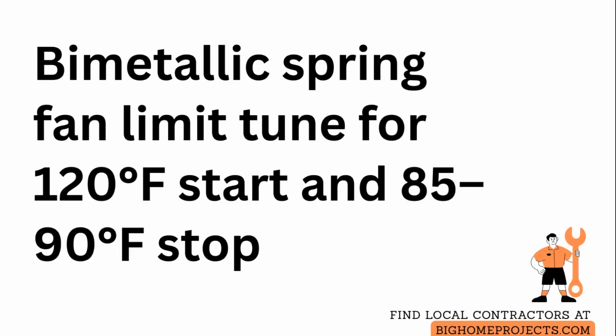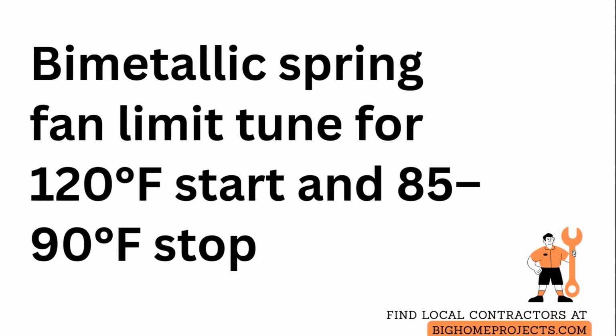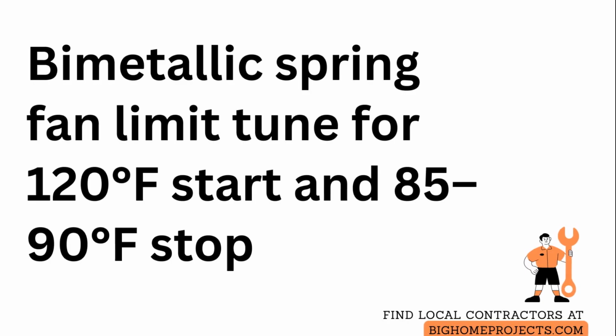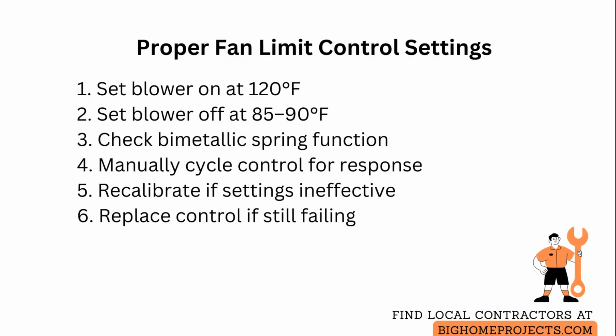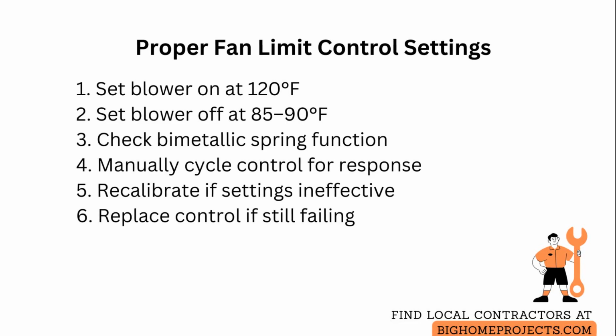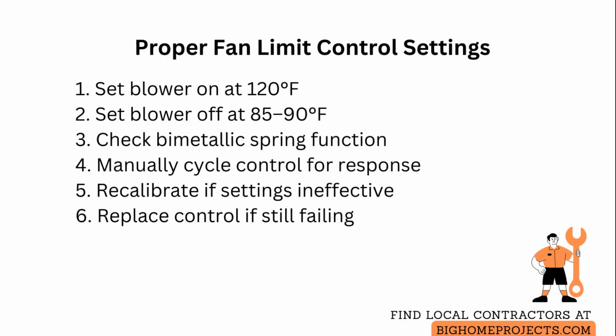Set the fan limit control so the blower only runs when furnace heat exchanger temperature requires it to move warm air into the house. Set the blower on point at 120 degrees Fahrenheit and the off point between 85 and 90 degrees Fahrenheit to allow proper heat transfer without unnecessary fan run time.